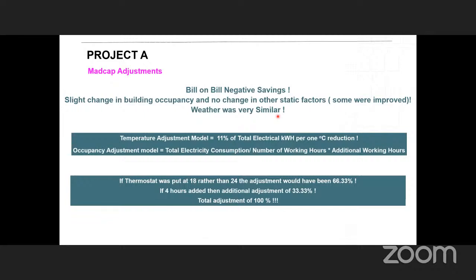And as you can see here, if we just do an example and say, well, if I put the thermostat at 18 degrees C compared to 24, then the energy consumption would jump by 66.33%. And if I add 4 hours in terms of working hours per day, then I increase the consumption by 33.3%. So if I do both, I have increased the baseline consumption by 100%, which doesn't make sense. If you put your thermostat at 18 degrees C from 24, it's not going to add 66% energy consumption. So that was one of the issues we found in this building, and the ESCO was just trying to save on the contract so that they don't have to pay for the guaranteed savings. They don't have to pay that penalty because they were not saving any energy. So we need to be very careful when doing these M&V plans or reviewing any, because we've seen that, and a lot of projects do go through that.